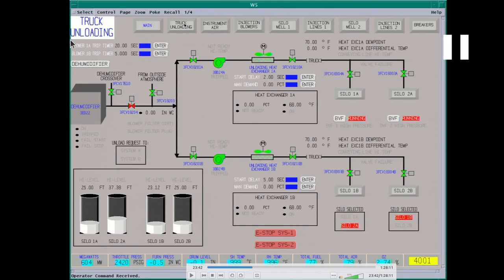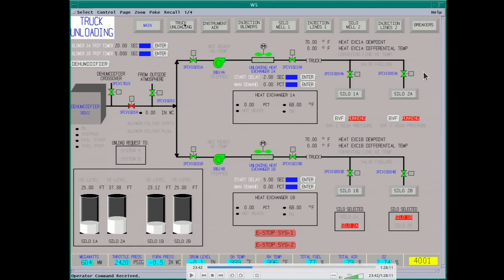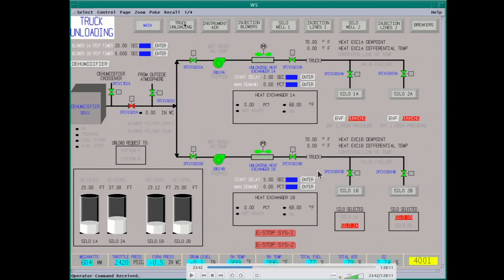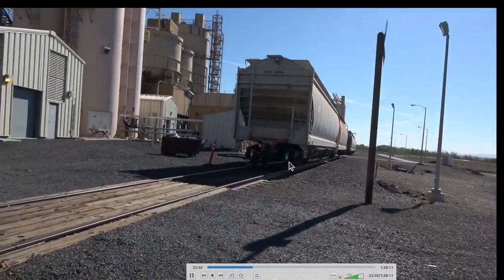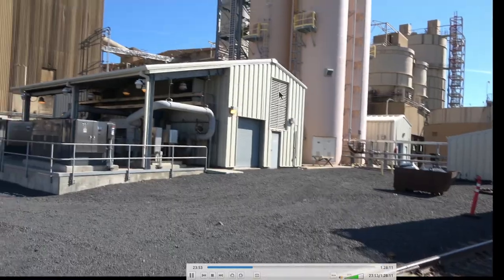This is the DSI — Dry Sorbent Injection System — using a Trona product. It's kind of like a baking soda/sodium bicarbonate-type product. You have a dehumidifier and blowers — any moisture in this product will plug it up. It comes in by rail cars — pneumatic cars — and also trucks. Air pressure is used to unload and blow them into these silos. There are chillers back here to dry the air — basically dehumidifiers with a wheel that turns: part of the wheel is heated and the rest absorbs the moisture.